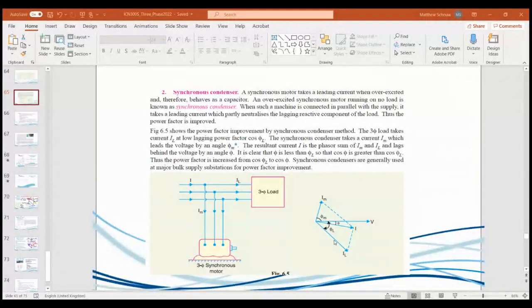Once we do motors, typically on a bigger scale like a power plant, they'll use synchronous motors instead of having a shitload of capacitor banks, because you can't have these massive capacitors to correct big voltages - you're talking about a lot of kVA. So it can be used as that, but what a synchronous motor is essentially good for is being a good constant speed motor.